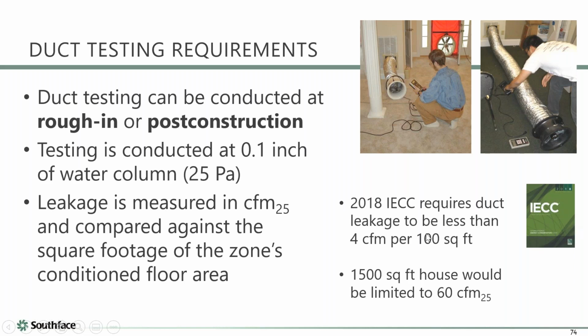You're allowed 4% duct leakage, and we'll talk about that in a second. Georgia backed off. We're actually 6%, but still pretty tight. And you can test ducts at rough-in, or you can test ducts at final. What you do is you essentially mask over all the supplies and returns. You connect your little duct testing fan somewhere into the system. Here they're connecting at the return. And you pressurize or depressurize the ducts to the test condition, which is 25 pascals.